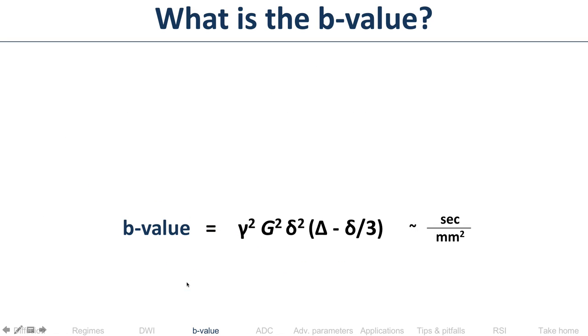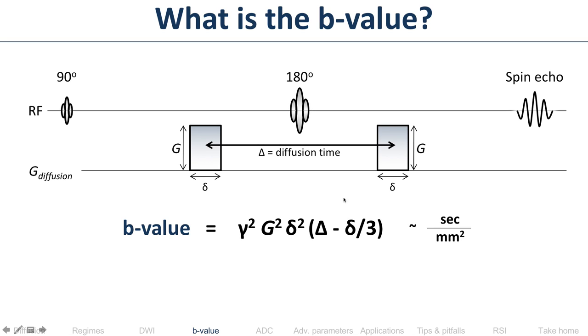The B value formula: B is proportional to the gyromagnetic ratio squared (constant for hydrogen at 42.6 MHz/T), the gradient amplitude squared, the gradient duration squared (with an arithmetic correction), and the diffusion time. So to make your B value higher, you can increase gradient amplitude, increase lobe duration, or increase gradient separation.